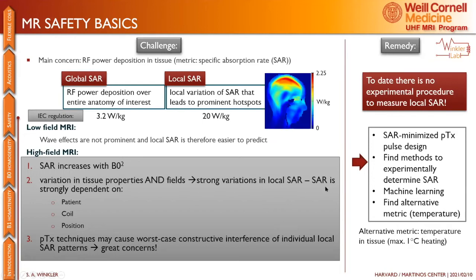But what's more complicated is that you can't really predict this. It changes based on the patient, based on the coil, based on the position. There are so many different aspects that go into it, and one simulation alone will not tell you much. So it's a hard problem. If you use PTX, you might even cause further problems, because you could have worst case constructive interference of electrical fields and therefore SAR. So that could be a big problem.